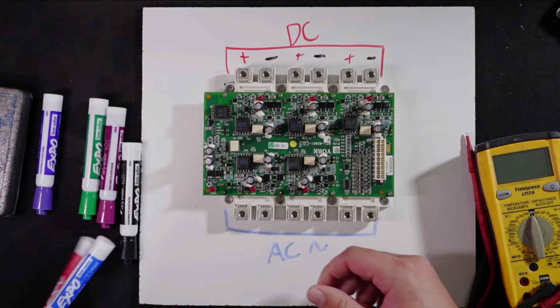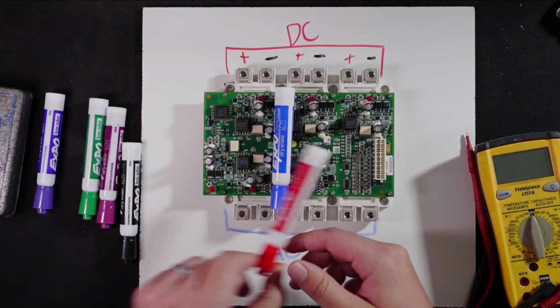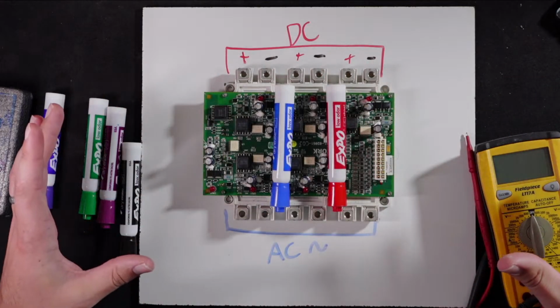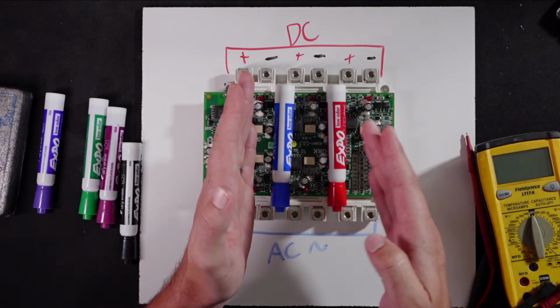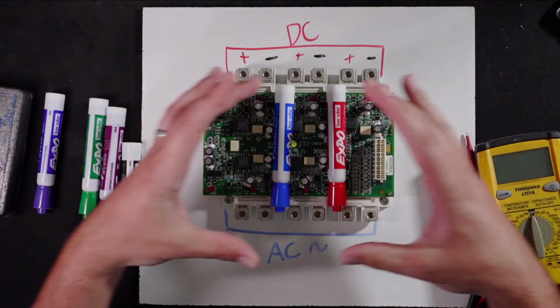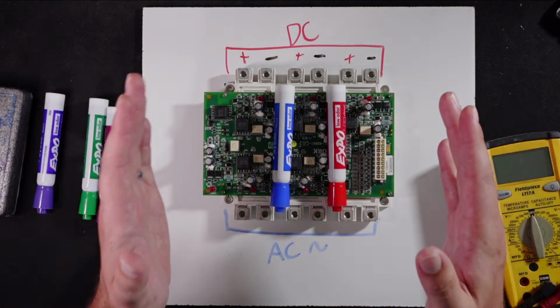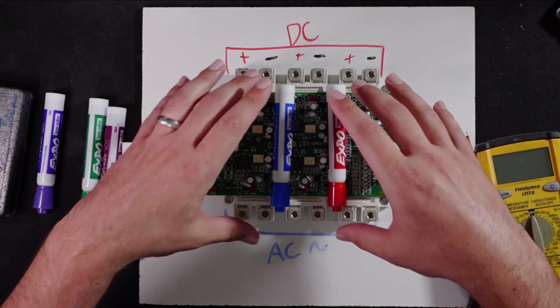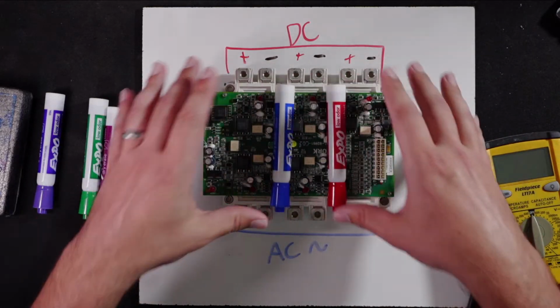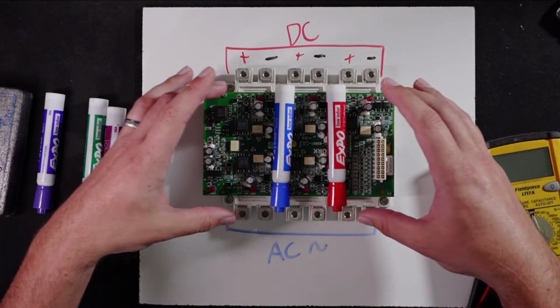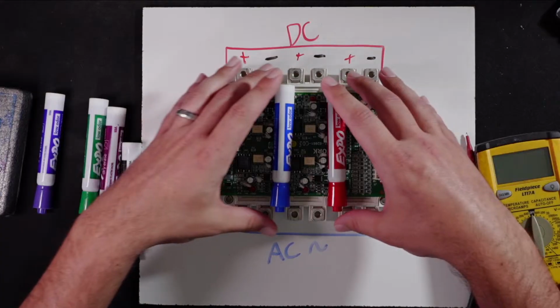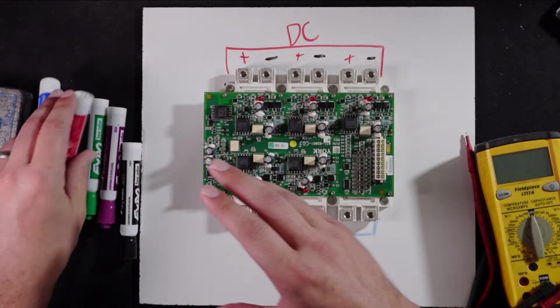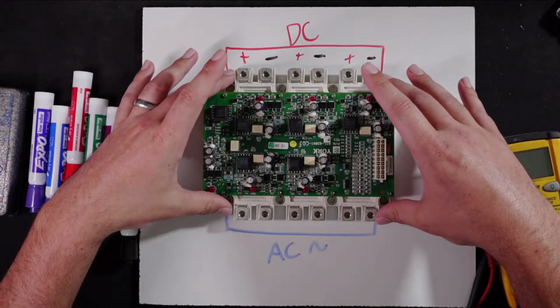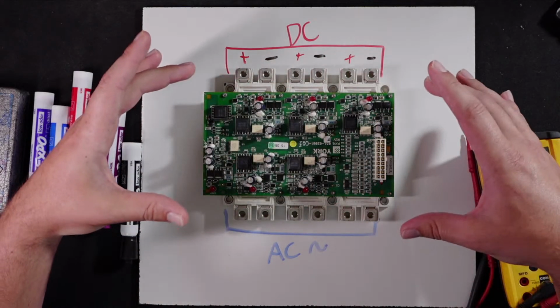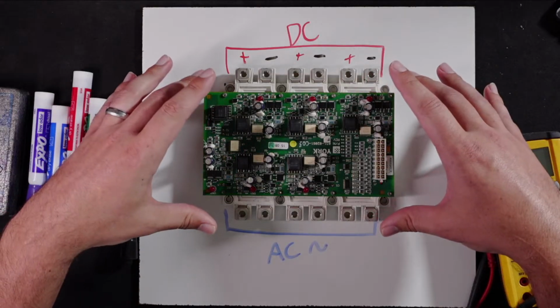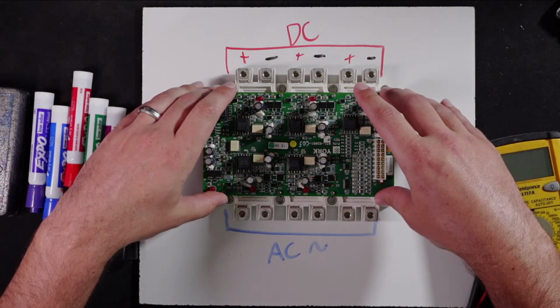Another thing to note with these is that we have individual gates. So right there is 3 gates, gate 1, 2, and 3. Now they're combined in a single module, but they are independent gates. They can function in unison, which is part of what the module is doing, allowing them to work together as one single unit. And we do this to help distribute power flow, because it's much easier to combine a series of smaller gates than it is to make just one big gate. It's far less efficient, and from what I understand, it generates a lot more heat.